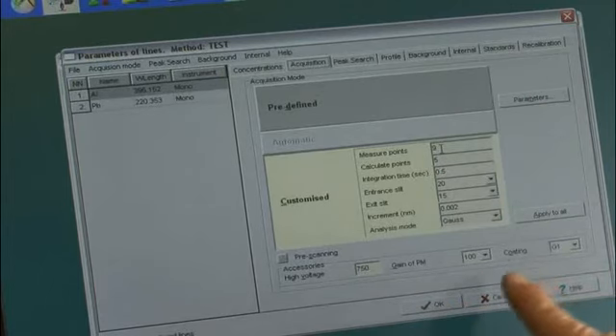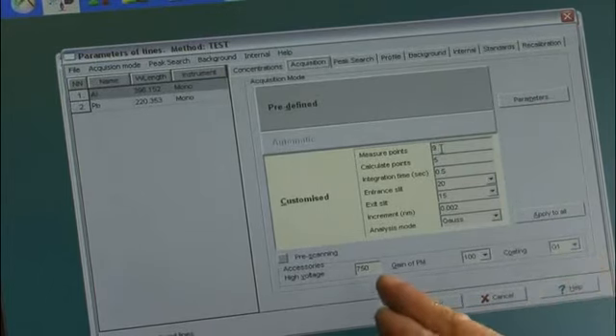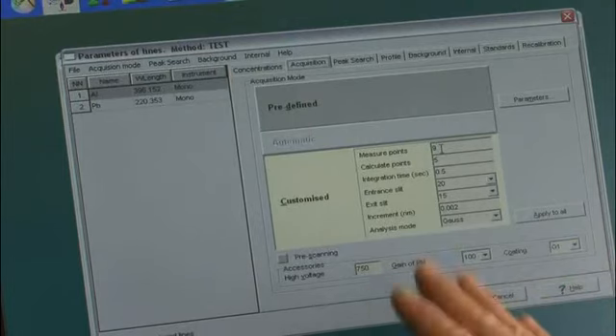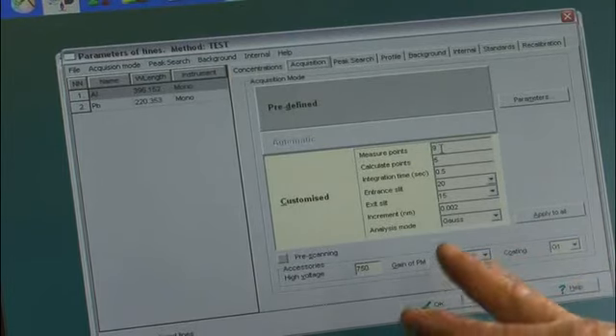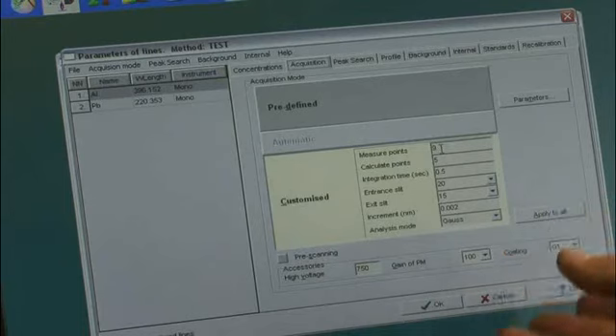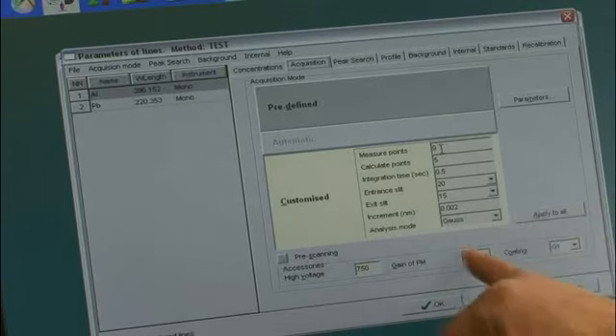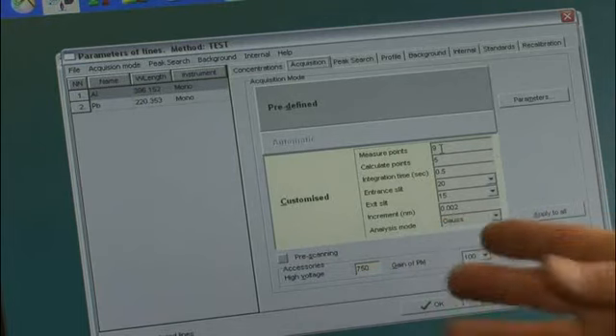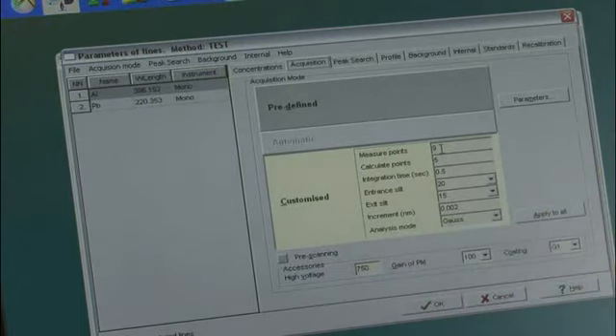Again, you don't have any gas control, but here you can set the voltage and the gain manually. What you normally do is something we call an auto attenuate, and it'll automatically set the voltage and gain for that concentration of that element. I'll show you how we do that.